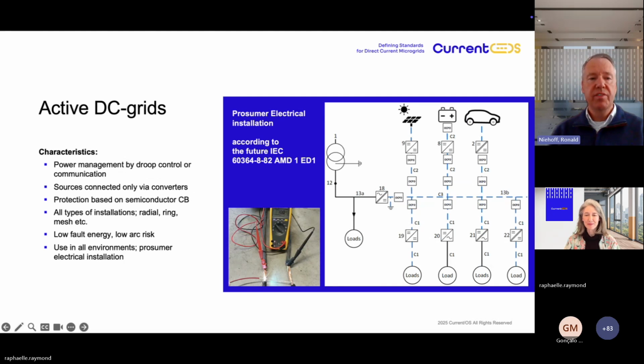And what is an active DC grid? The term active in electrical has several meanings, mainly to indicate that circuits are live, but we are using the term active as an indication that there is power management through control or communication. There are sources connected in such circuits only via converters, so not direct connections. The protection is based on semiconductor circuit breakers, and all kinds of installations are possible.